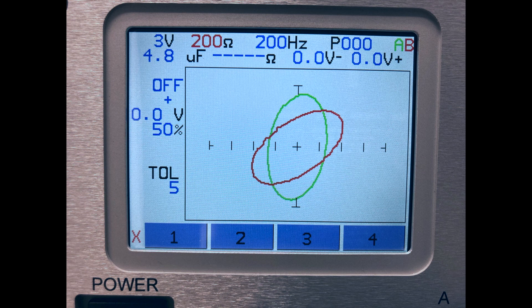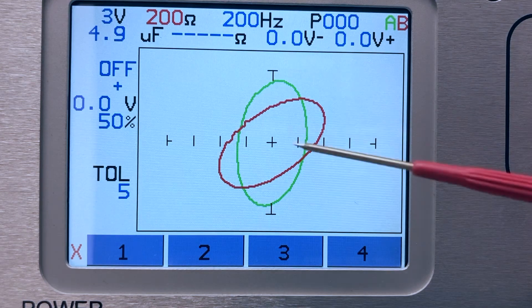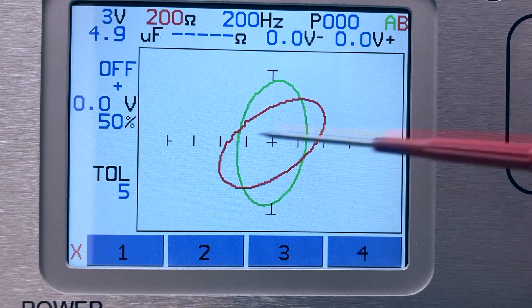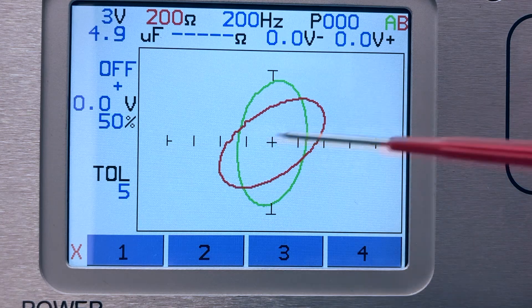Degradation in capacitors is a common problem. This signature in green shows a good 100 microfarad capacitor compared to a degraded one shown in red. Note the change in width and angle. This type of failure is sometimes referred to as leakage.